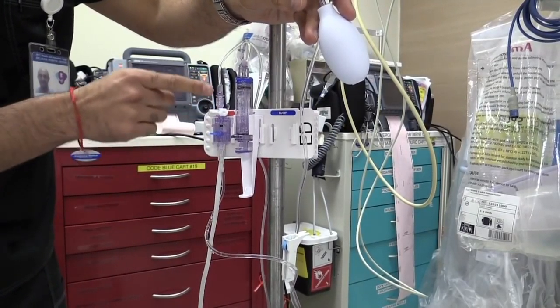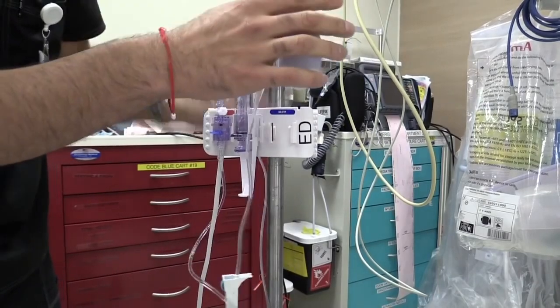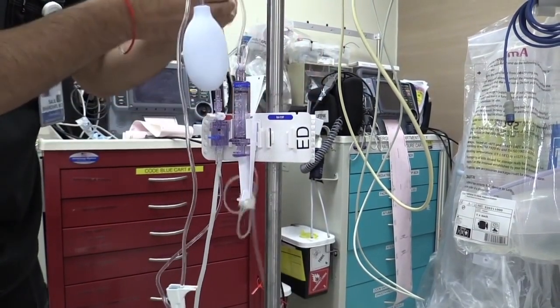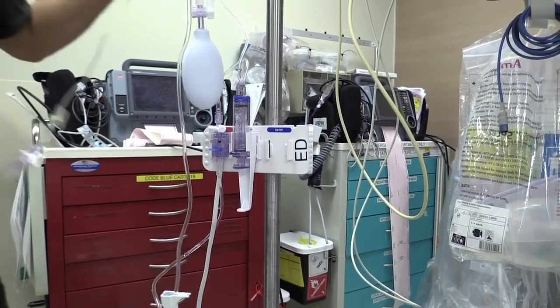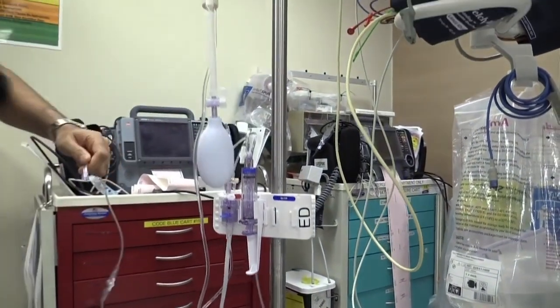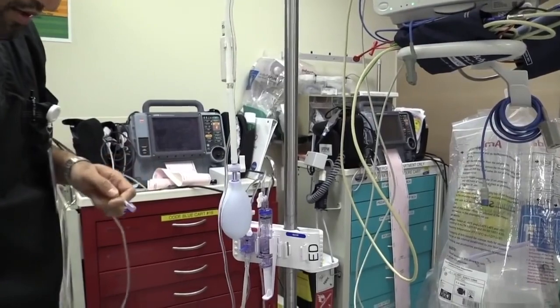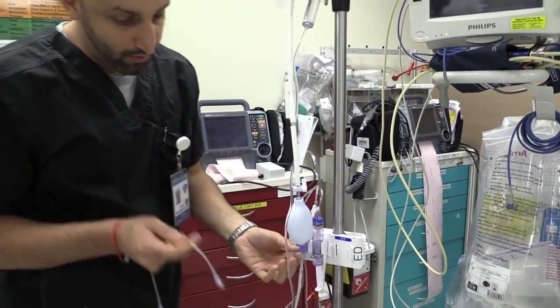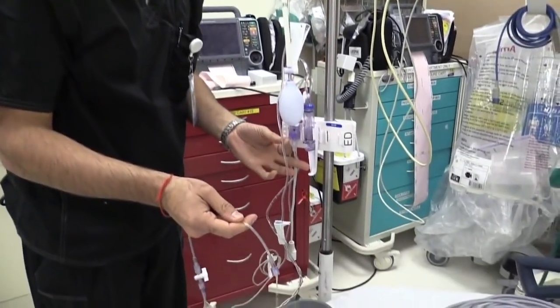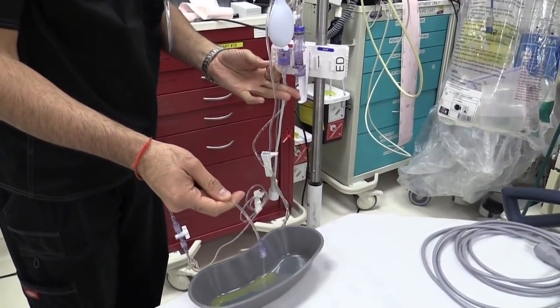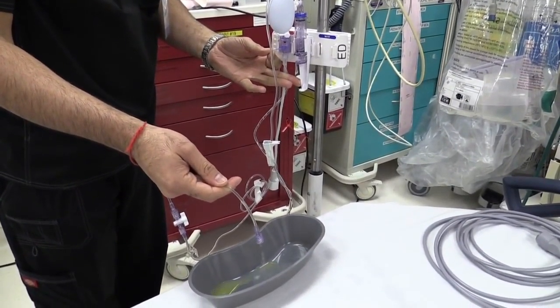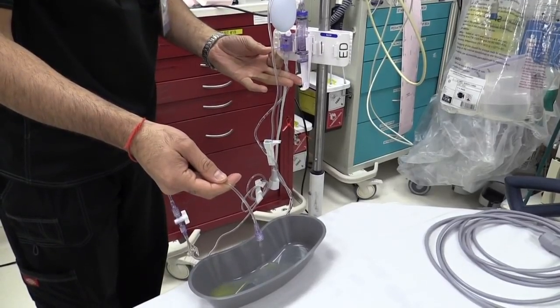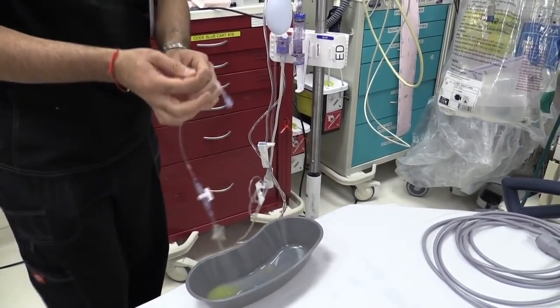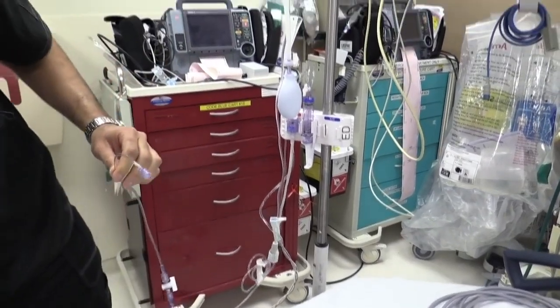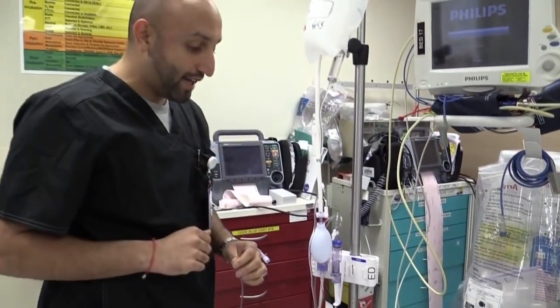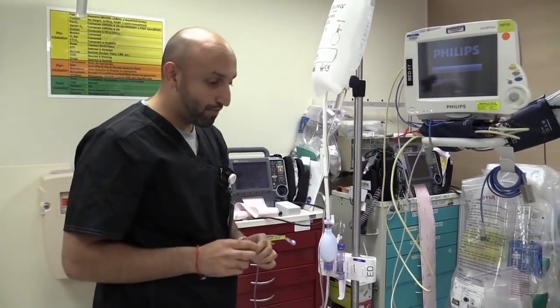Now we're going to take out all the air from here all the way towards the end of the IV tubing that goes towards the patient. And essentially you're going to do the same thing. We'll get a little basin just to make sure we are clean on this part, and we'll do the same thing. We'll pull on the tab and make sure that IV tubing is clear of any and all air bubbles, and as soon as that's done, boom, we are done. So now all of the air bubbles are essentially out of the IV tubing, and now we're ready to connect it to our monitor.